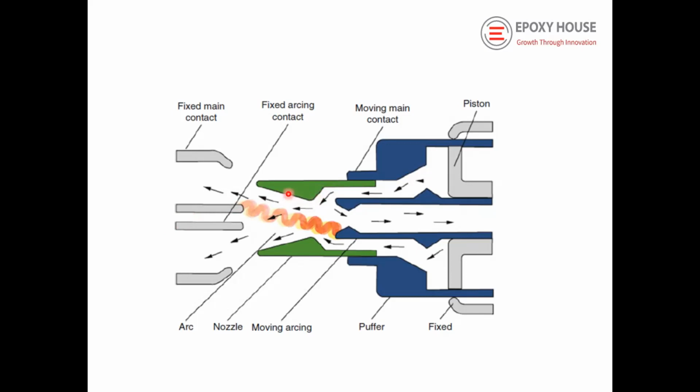If this angle changes, it will lose its properties. For that reason, people are working a lot on replacing this material with a different composition. The efficiency of arc extinction is also being improved by coordinating the mechanism with the movement of this, so it is a fully coordinated movement of the breaker moving rod with respect to this profile.